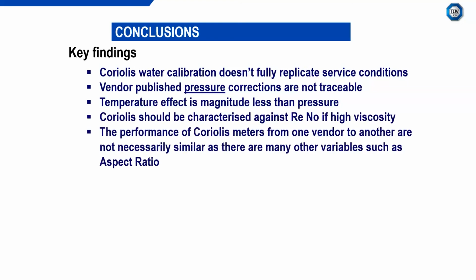This is crucial, this point here. The performance of Coriolis meters from one vendor to another is not necessarily similar. There are many other variables such as aspect ratio, R&D, even just the history of them producing it, working out if there is a pressure effect, temperature effect, correcting for it, the design, the frequency at which they oscillate. There's a lot of different things that affect Coriolis meters, so it's not true to say that they're all the same. They differ from vendor to vendor.